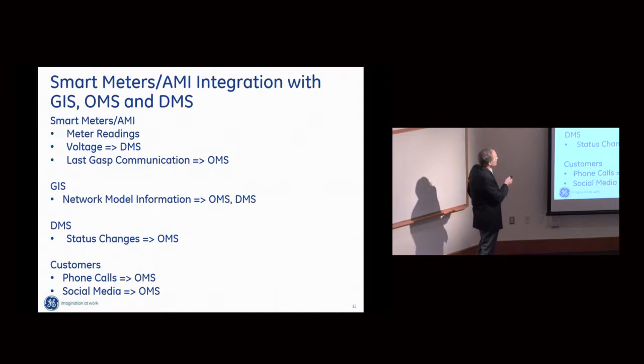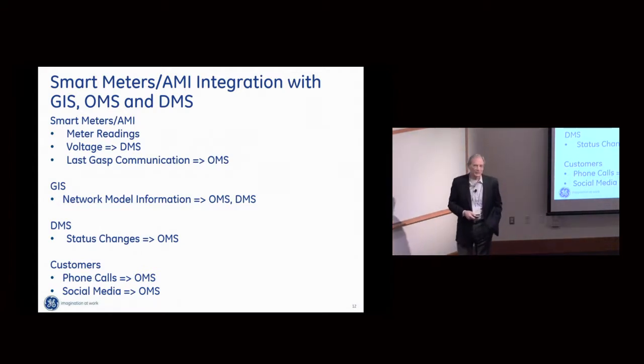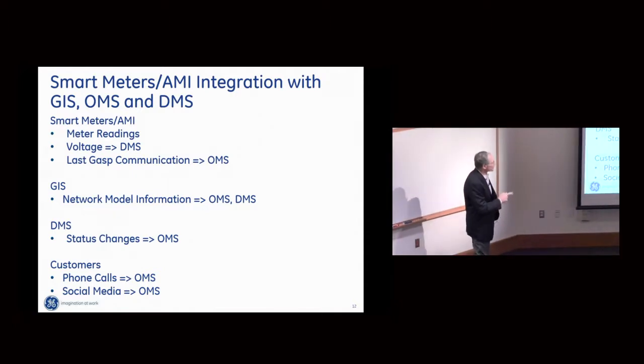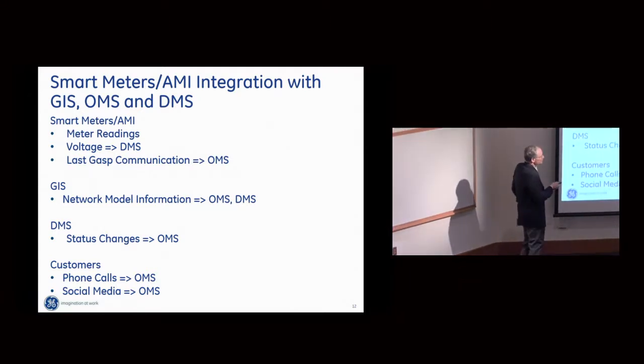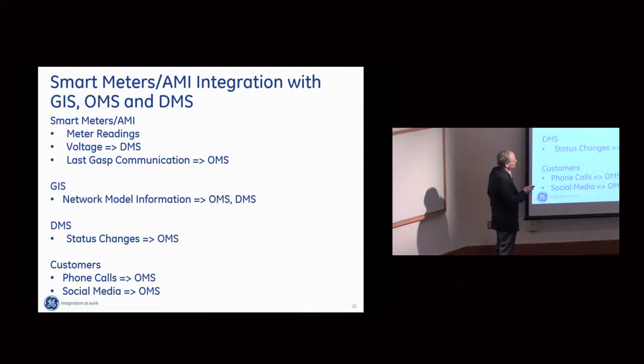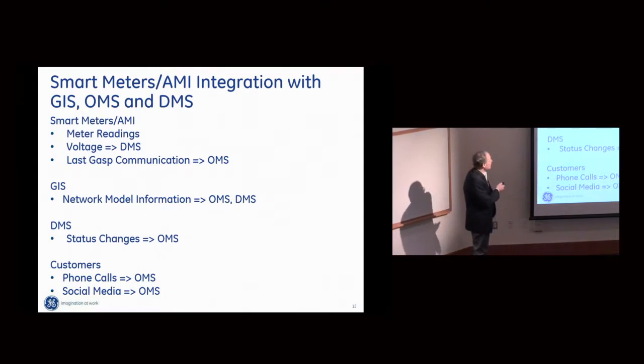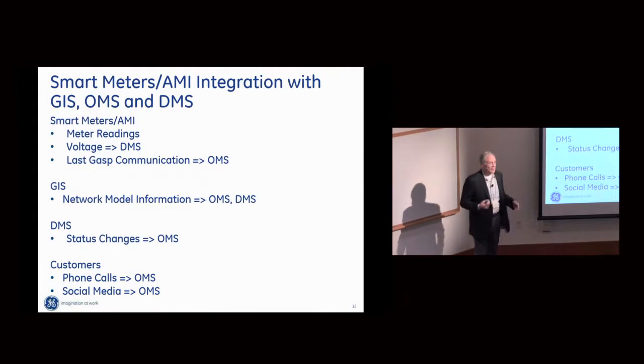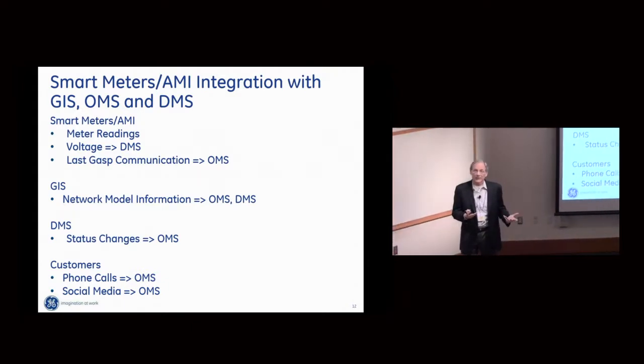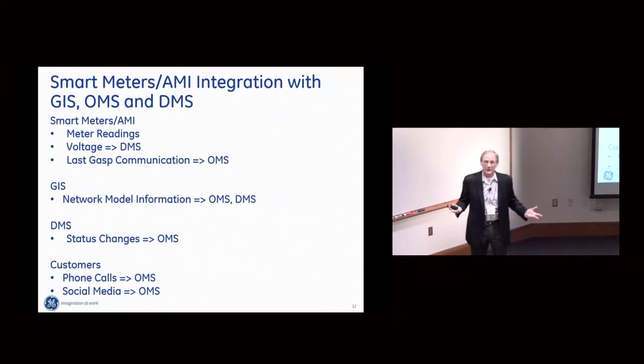The geographic information system is the reference system for the network model used by the OMS and DMS. About 15 years ago, we started taking all the status changes from the distribution SCADA system and tying those into the outage management system. Because the OMS has the network model and knows which customers are connected to which feeders, if it learns that a distribution feeder breaker tripped, that one piece of information tells the OMS which customers are on that feeder and now without electricity.